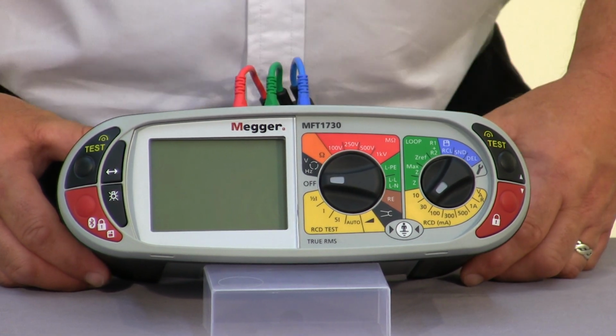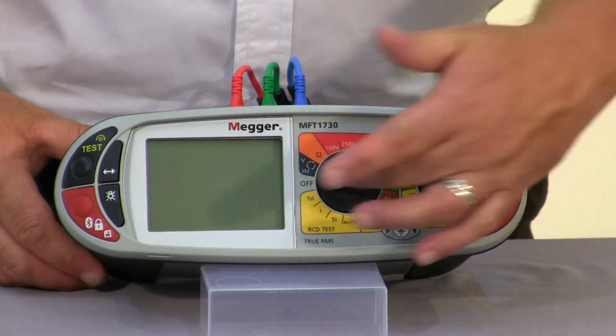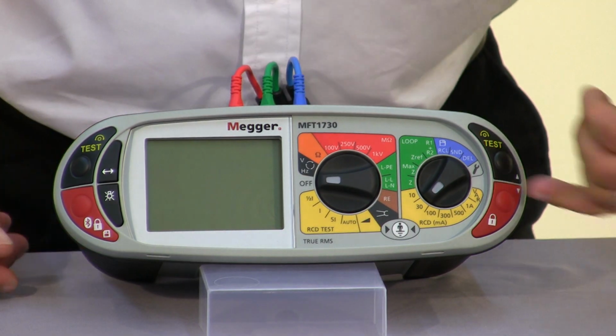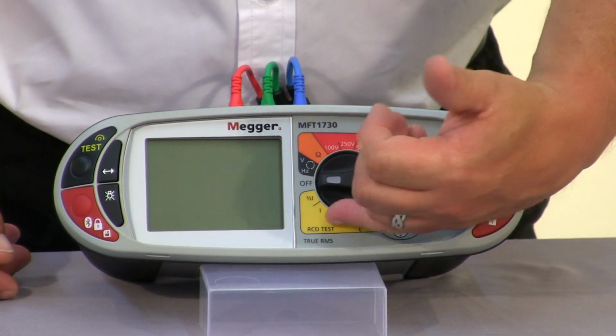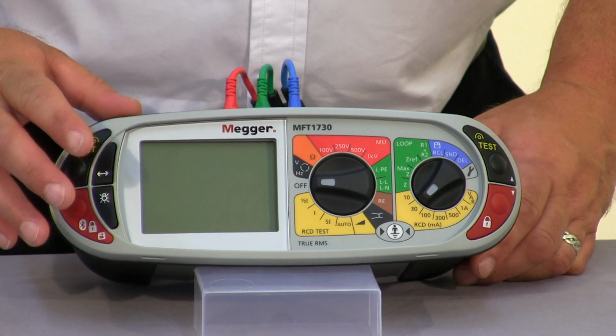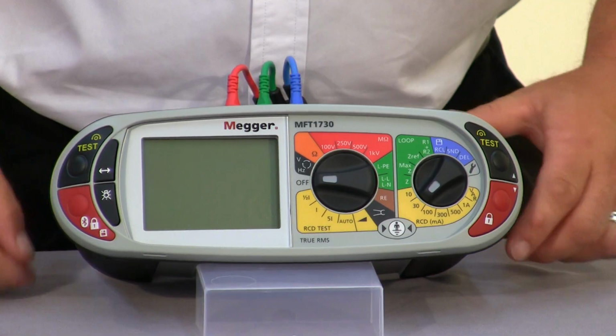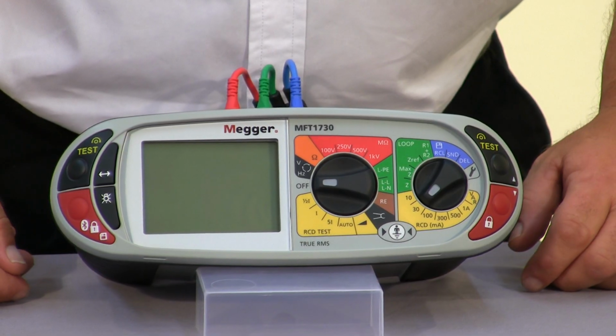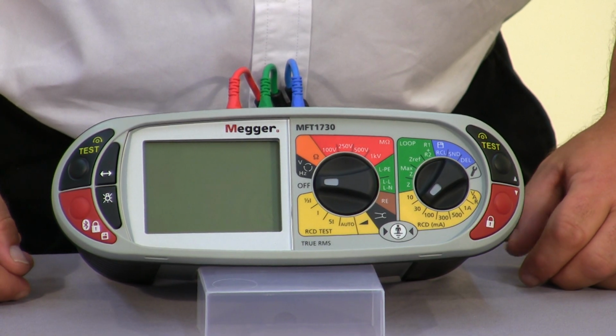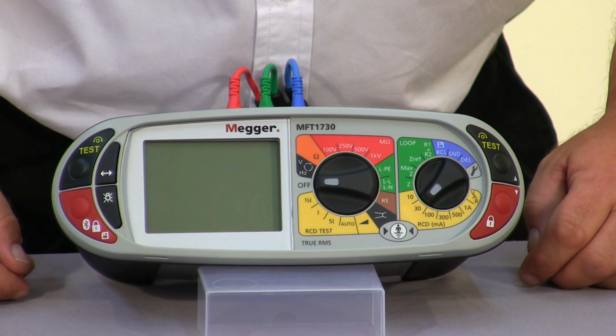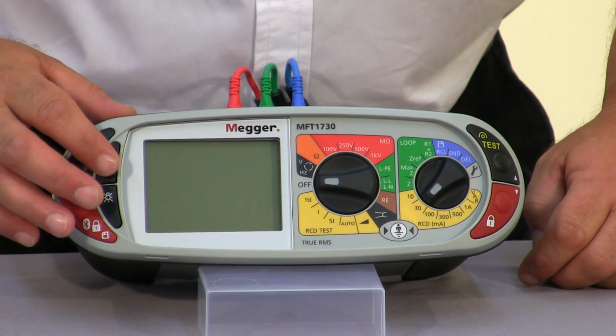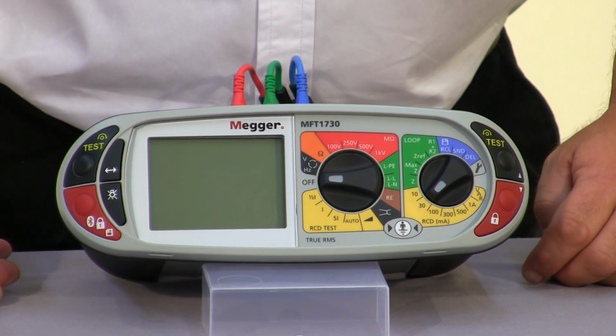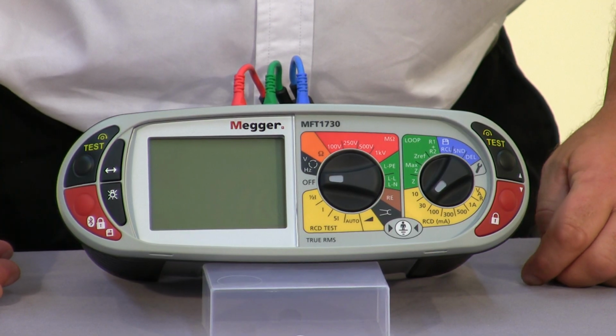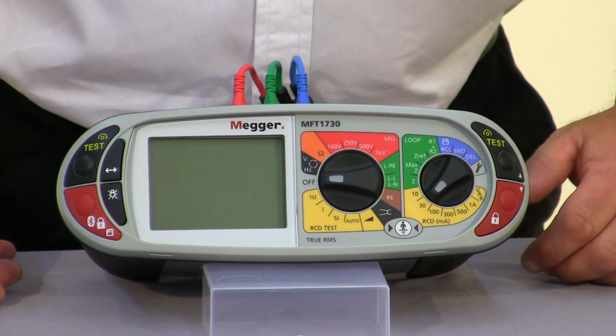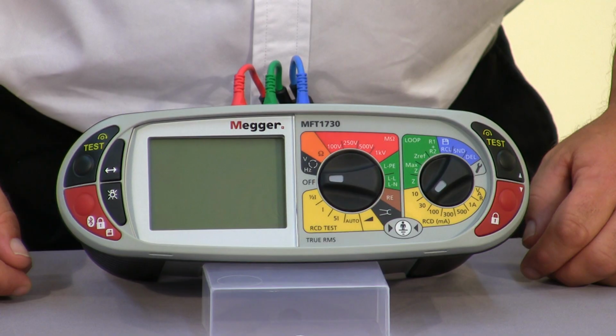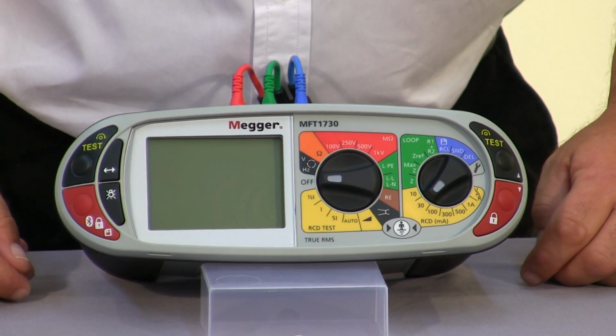Okay, so let's look at the RCD test functions. On the right hand switch, as you can see, we can select straightforward times half, times one and times five, and by pressing the function key on the front, we can select whether or not we're going to test on 0 or 180 degrees, either the rising or falling side of the waveform. Pressing and holding the function key will allow us to cycle through the different types of RCD, type A, type AC, selective variants of either of those, or the type B breaker.